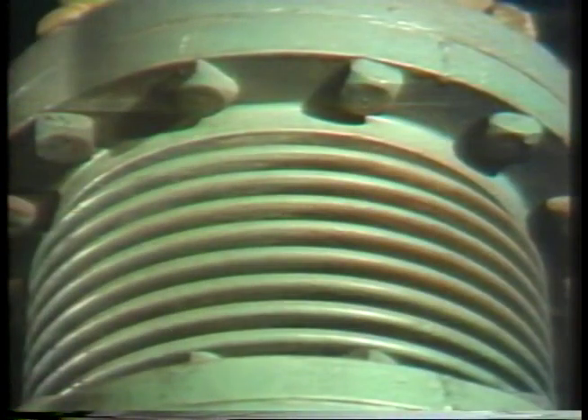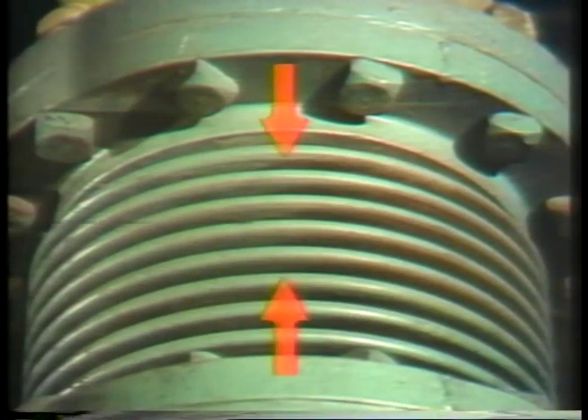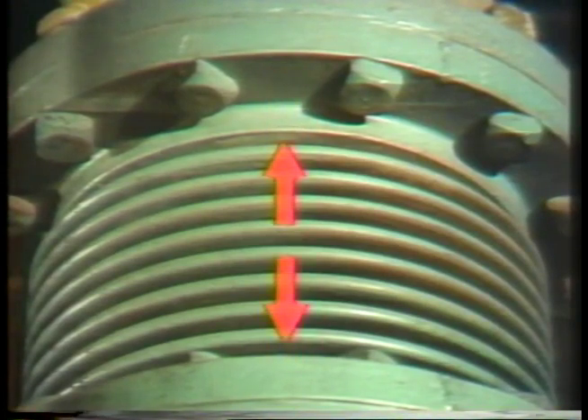The corrugated center is made of a strong but pliable material which allows the motion that results from expansion and contraction of the pipe. As the pipe gets hotter, it expands and becomes longer, pushing the corrugation together. When the pipe cools, it contracts, and the corrugations are elongated. Both expansion loops and expansion joints allow for expansion and contraction of piping systems. However, other plant components must also be designed and equipped to allow for the effects of temperature changes.